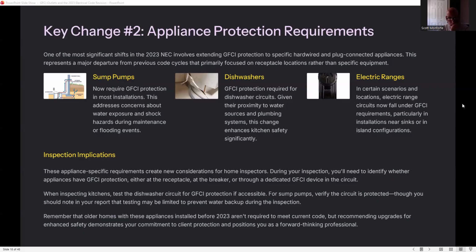So when Scott, Stan, and I were putting this together, I addressed the sump pumps. When I inspect and I don't see a GFCI outlet on a sump pump, I do point it out in my report, obviously, because it needs to be. But I too tell my client, it's not going to be in the report, but I'm going to tell you personally, you may not want to have a GFCI outlet on a sump pump. The moisture coming up could trip it. Just the high moisture in a basement can trip it. So I always want my sump pumps running.